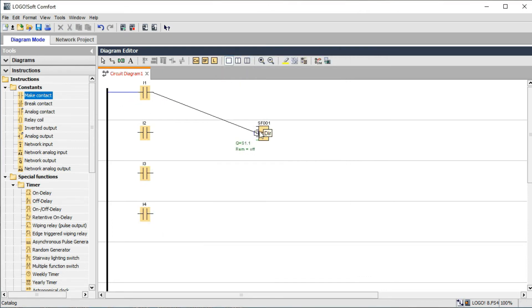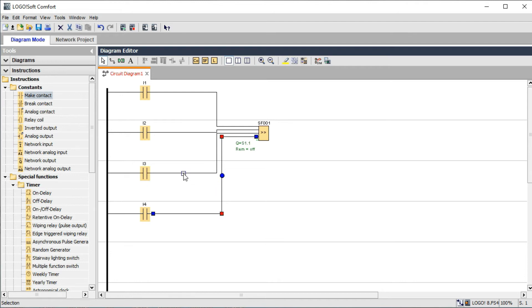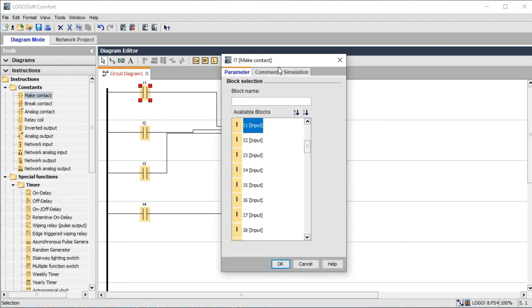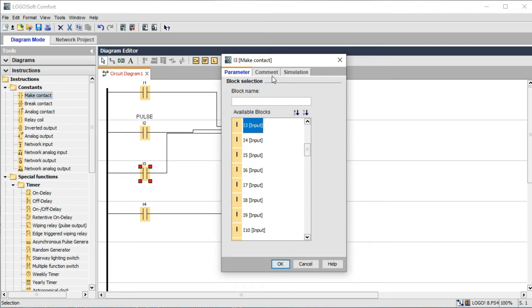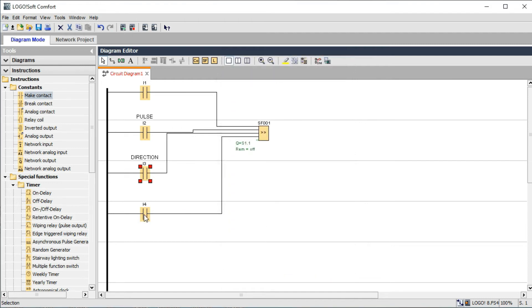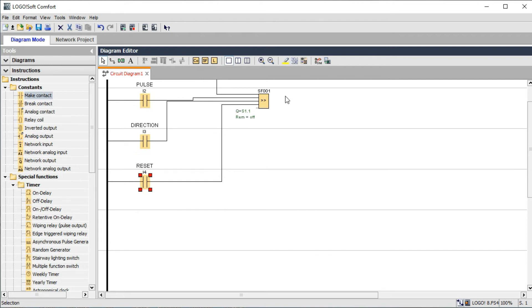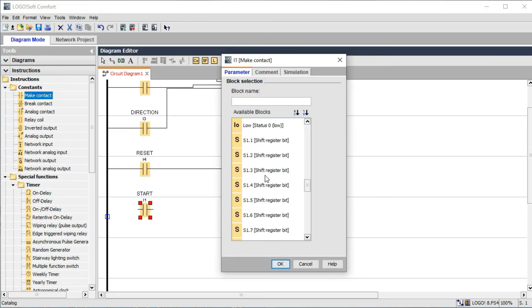In the programming, we use make contacts. The sensor input I1 is connected to IN — that means when your program starts, the devices are activated. I2 is connected to Trigger for the pulse. The Direction input controls the direction. I4 is the reset point. These contacts are not connected to each other — the main topics here are: I1 for start, I2 for pulse, the direction input for direction control, and I4 for reset.